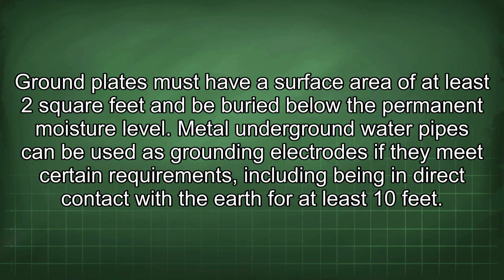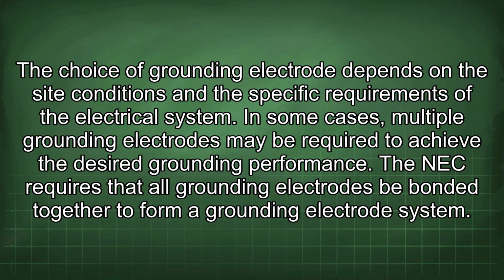Metal underground water pipes can be used as grounding electrodes if they meet certain requirements, including being in direct contact with the earth for at least 10 feet. The choice of grounding electrode depends on the site conditions and the specific requirements of the electrical system. In some cases, multiple grounding electrodes may be required to achieve the desired grounding performance. The NEC requires that all grounding electrodes be bonded together to form a grounding electrode system.